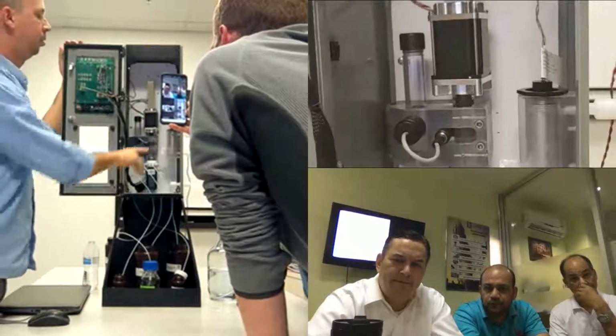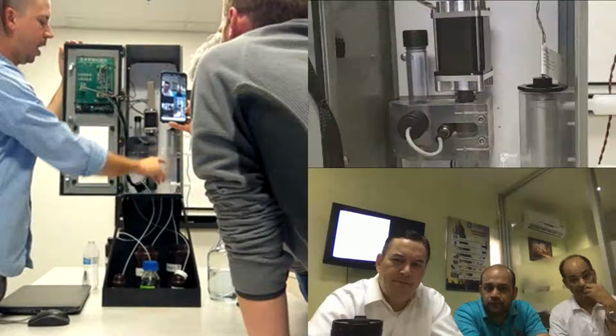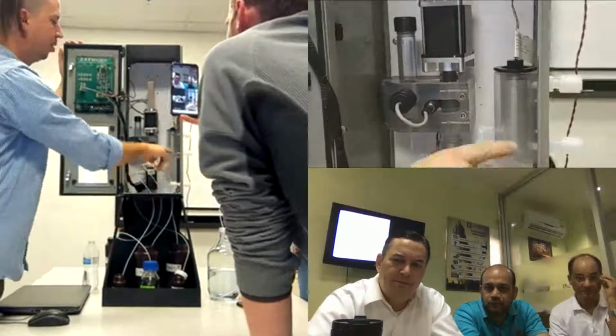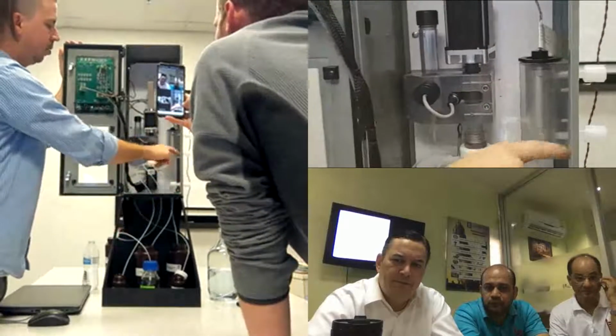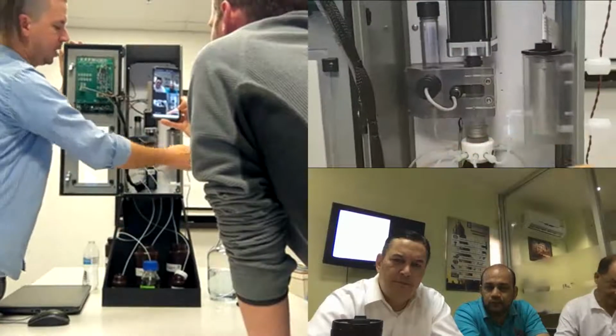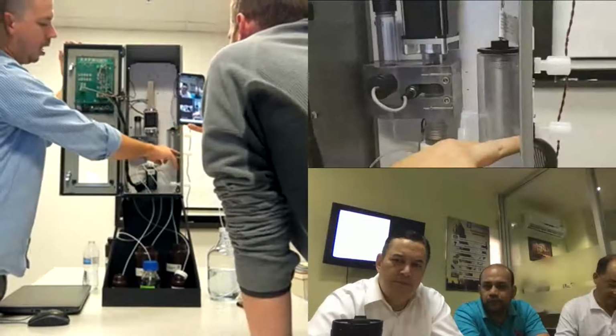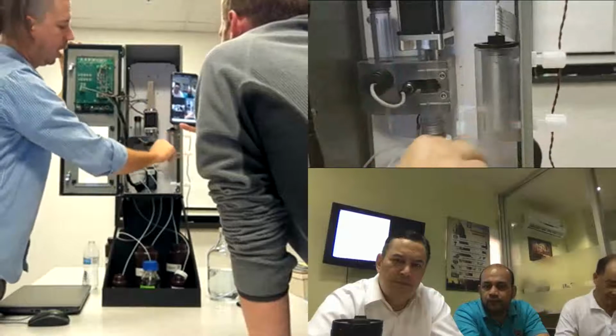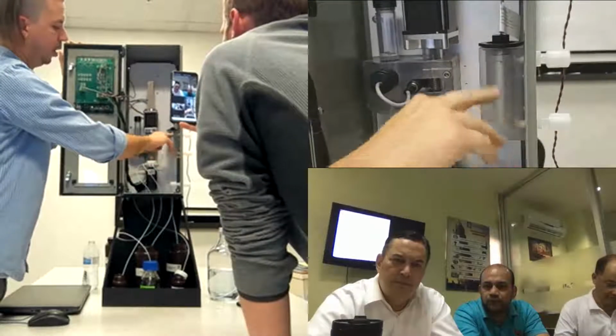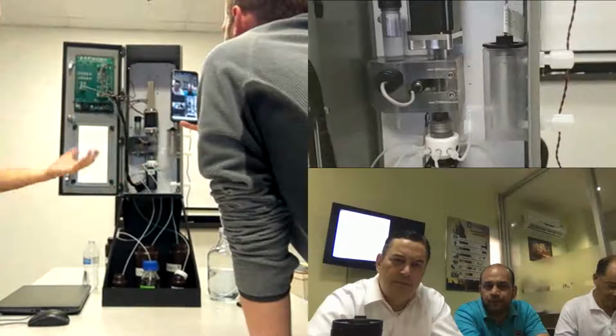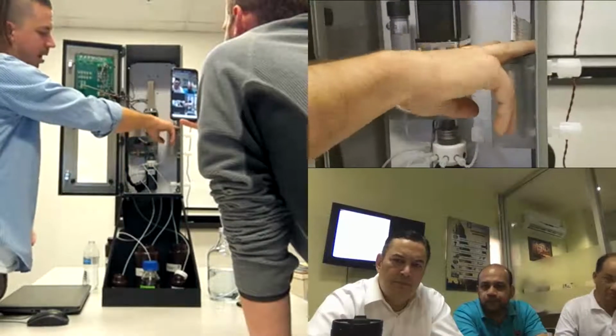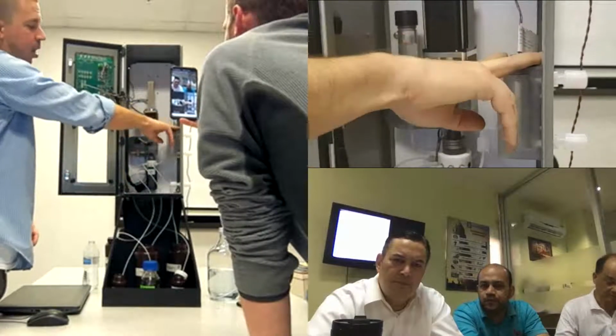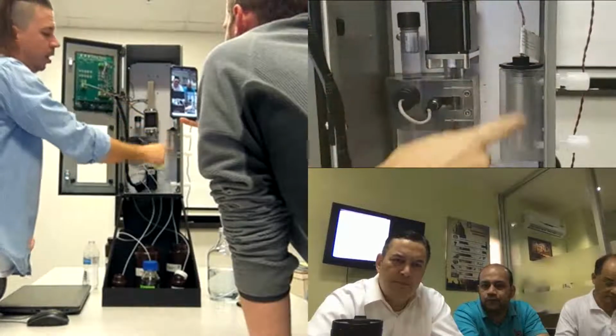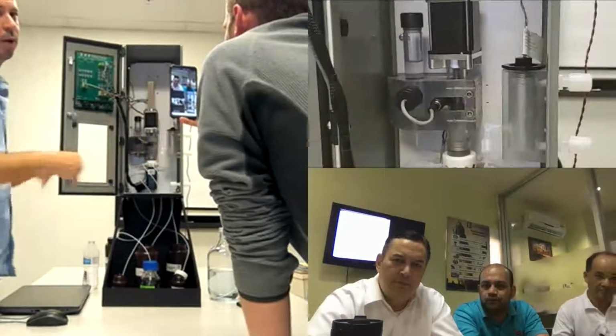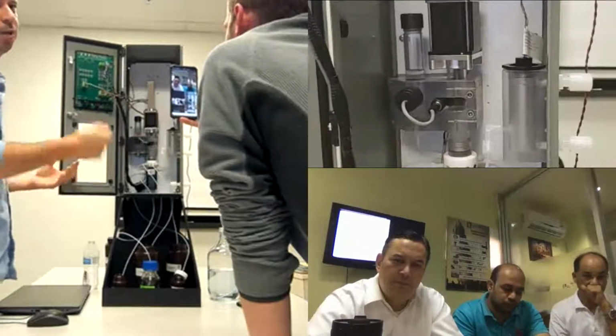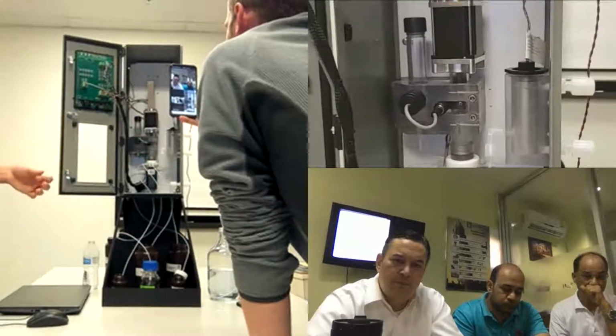This right here we're not using right now because we don't have pressure motivating the liquid through the system, but this is actually our fast loop for the side stream connections. We have an alarm on that as well—if the customer's fluid isn't being pumped through the system, we monitor that with a little level sensor. If this sensor senses there's no liquid in this volume, we know we can't make an accurate measurement, and we set off an alarm for that too.